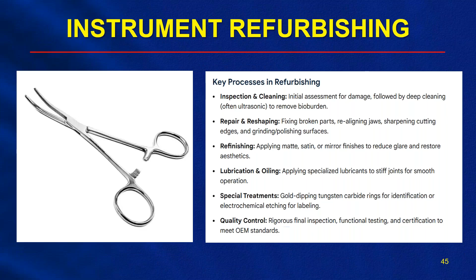Lubricating and oiling, which would be applying specialized lubricants to stiff joints for smooth operation. Any special treatments such as gold dipping, tungsten carbide rings for identification, or electrochemical etching for labeling. But basically, the main thing is quality control: rigorous final inspection, functional testing, and certification to meet OEM standards. They're getting these instruments back to original manufacturer standards.